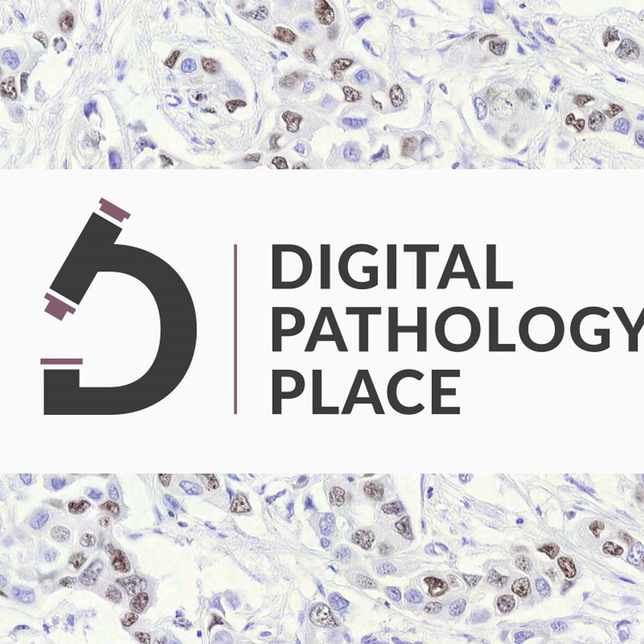And 510K clearance is a pre-market submission made to the FDA to demonstrate that a device, including software as a medical device, is at least as safe and effective as another legally marketed, similar device, right? So one scanner is showing, oh, I'm as good as the other scanner. The word used here is non-inferior, and in regulatory speech it's going to be non-inferior. What they need to show is that they actually are like the other device, and they have to show transparency about the data used for training and validation. This is important. Also, any foreseeable risks associated with the AI machine learning software as a medical device within routine operations, right?